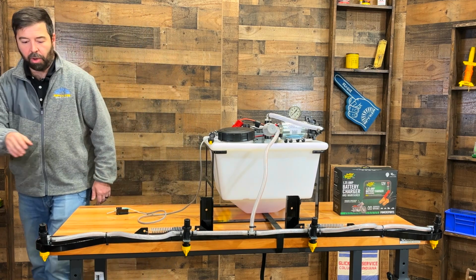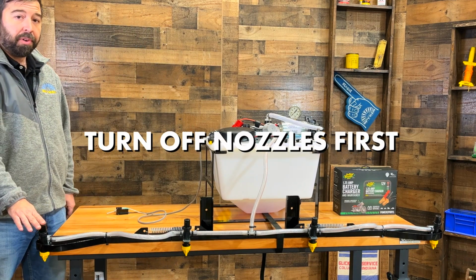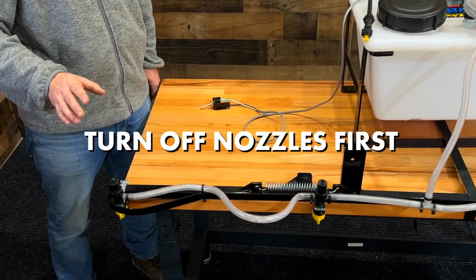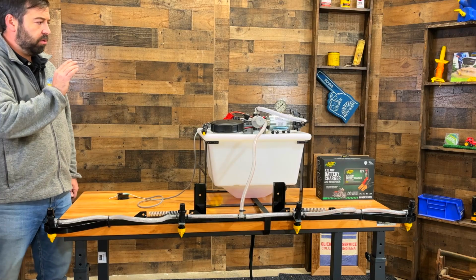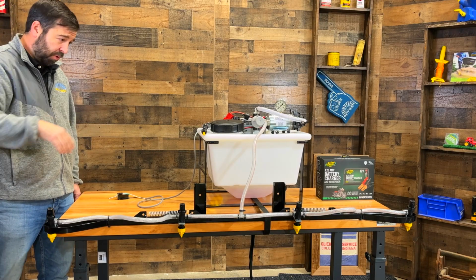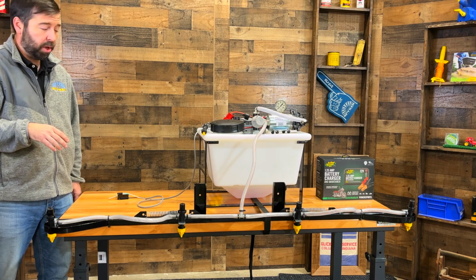Again, it's best to go ahead and turn off all the nozzles first to control the amount of spray that comes out when you're testing. What we're going to do is turn the pump on and check every nozzle individually to see that it's properly working.